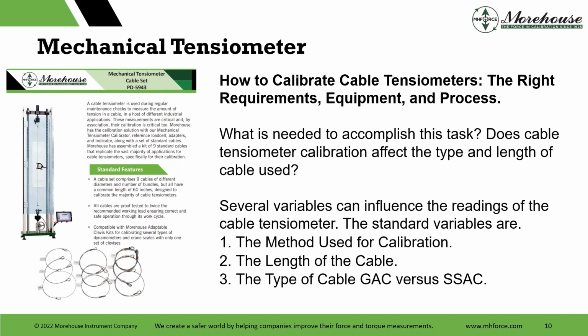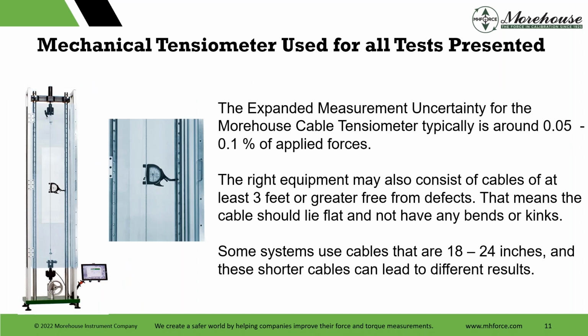Everything comes with it. You have multiple load cells. You can do all kinds of stuff with that. Load cells, handheld force gauges, all the other things and everything you need to do. We put a lot of work into designing that. Expanded measurement uncertainty, typically around 0.05 to 0.1% of applied force, depending on the resolution of the UUT that impacts that best existing device. Right equipment also consists of cables at least 3 feet or greater free from defects, which we'll talk about. That means the cable should lie flat and not have any bends or kinks.